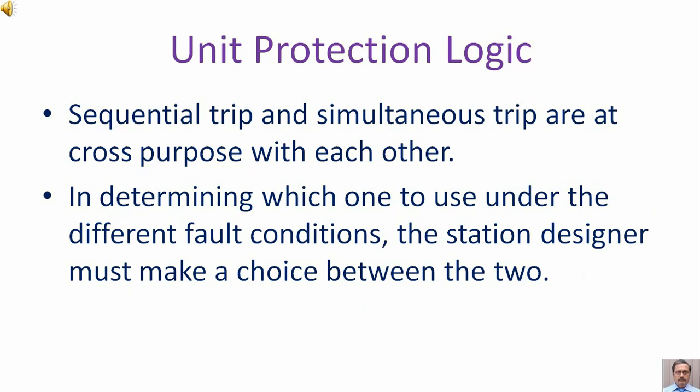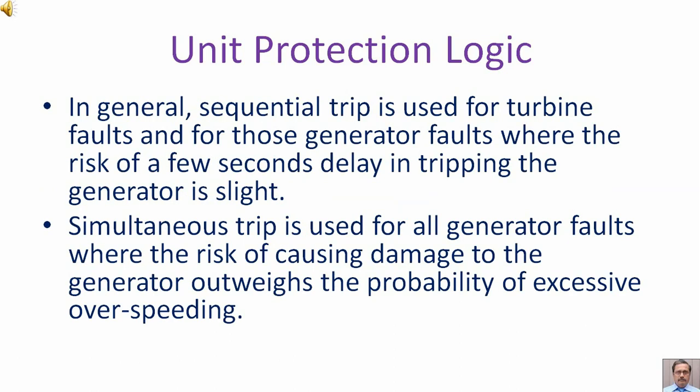Sequential trip and simultaneous trip are at cross purposes with each other. In determining which to use under different fault conditions, the station designer must make a choice between the two. In general, sequential trip is used for turbine faults and for those generator faults where the risk of a few seconds' delay in tripping the generator is slight. Simultaneous trip is used for all generator faults where the risk of causing damage to the generator outweighs the probability of excessive overspeed.